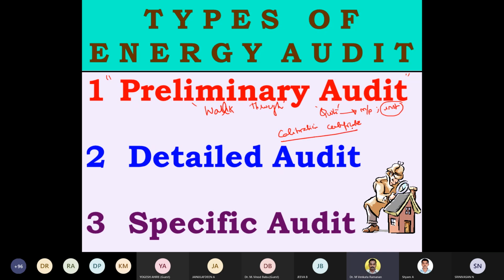Instruments that energy auditors own will often be quite old, and the values they show will have inherent errors. Just a 1 degree centigrade difference can affect the COP of an air conditioning plant hugely, or affect the kW per TR. You might even end up branding equipment as inefficient though it operates well, because of instrument inaccuracy - leading to wrong diagnosis and unnecessary replacement. So we advise that when you go for an energy audit, insist on calibration certificates for the consultant's equipment.